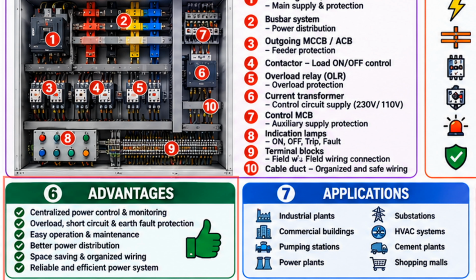Now let's talk about the advantages of using a power control center. The first advantage is centralized power distribution. Instead of connecting every load directly to the transformer, the PCC organizes the entire electrical system from one location. The second advantage is better protection. Modern protection devices can quickly detect electrical faults and disconnect the faulty circuit before serious damage occurs.